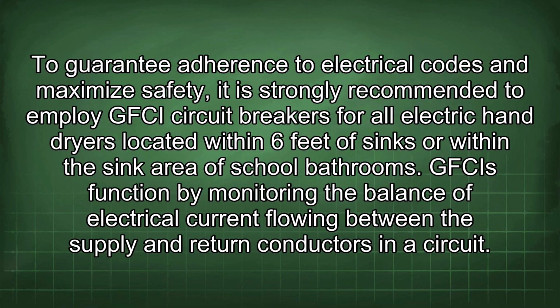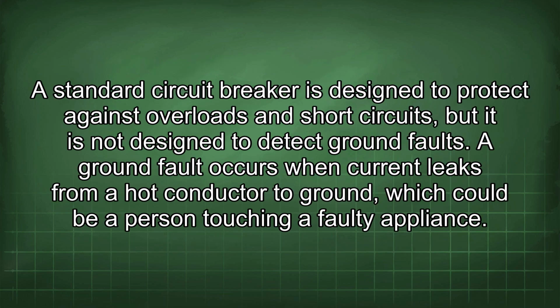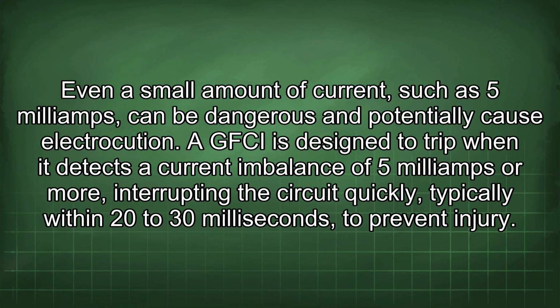GFCIs function by monitoring the balance of electrical current flowing between the supply and return conductors in a circuit. A standard circuit breaker is designed to protect against overloads and short circuits, but it is not designed to detect ground faults. A ground fault occurs when current leaks from a hot conductor to ground, which could be a person touching a faulty appliance. Even a small amount of current, such as 5 mA, can be dangerous and potentially cause electrocution. A GFCI is designed to trip when it detects a current imbalance of 5 mA or more, interrupting the circuit quickly, typically within 20 to 30 milliseconds, to prevent injury.